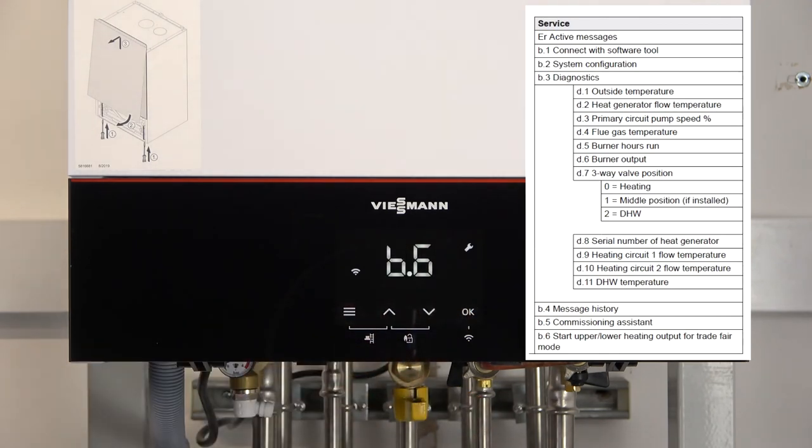Just a quick note on putting your boiler into high and low. When you put your boiler into high, it will go to what you've range rated the boiler to. So as we'll see in the other video, in B2, in our system configuration, we can range rate the boiler from all the way down from 32 kilowatts for a 35 kilowatt combi boiler right the way down to 3.2 kilowatts. So if you do, however, set your range rating for your maximum output to, say, 4 kilowatts, when we come into B6 and put it into high, it will only go to what we've range rated it to. The reason we do that is because if you're putting this boiler, this combi here, you've chosen for your 35 kilowatt option for your hot water delivery where it's in a smaller property with a heat loss of 4 kilowatts, then you can range rate it down to 4 kilowatts. You wouldn't want to send 32 kilowatts of heat down to that 4 kilowatt system. So that's the reason why we've done that.